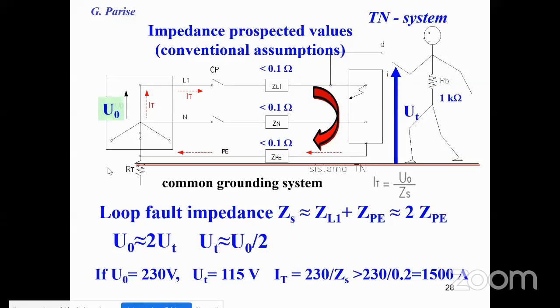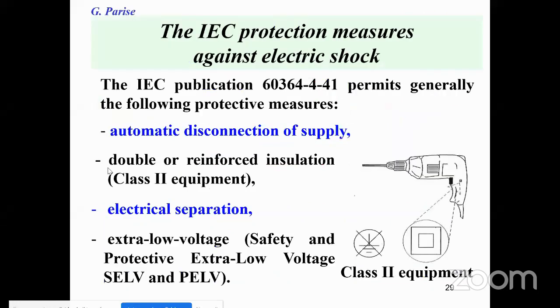Differently from the TT system, where we considered about 10 ohms, in this case the impedance is 0.2 or lower than 0.2 ohms. And so the fault current assumes a very high value, of the order of hundreds of amps, in this case 1,500 amps. These are very important considerations.